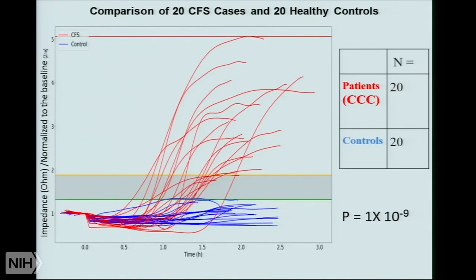The other thing I just want to show you is a diagnostic test that we've been working on called the nanoneedle. This is an old slide, but it just illustrates this a little bit. This is a device which has nanofabricated electrodes, uses a drop of blood, and measures electrical impedance. It's a very sensitive instrument. We have 2,500 electrodes per centimeter, and we sample each electrode 200 times a second. So it gives you a massive amount of data.